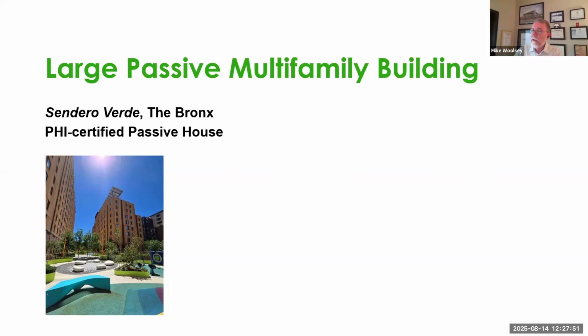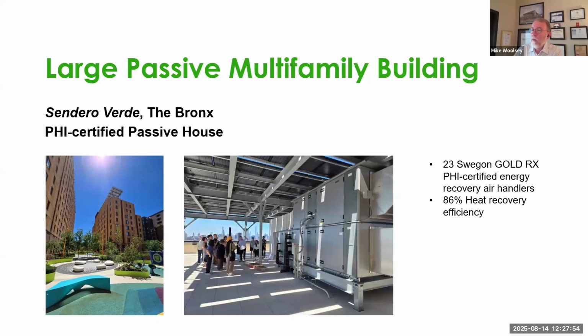This picture shows one of 23 such ERVs on the project. They're all PHI certified, all around 86% heat recovery efficiency. You can see lots of pipes sticking out of it, because there's a heating and cooling section integrated with the VRF system in this building. That's something we work with VRF manufacturers to accomplish. We're not linked to anyone in particular - we don't make our own VRF system, but we're happy to work with anybody else's VRF equipment.